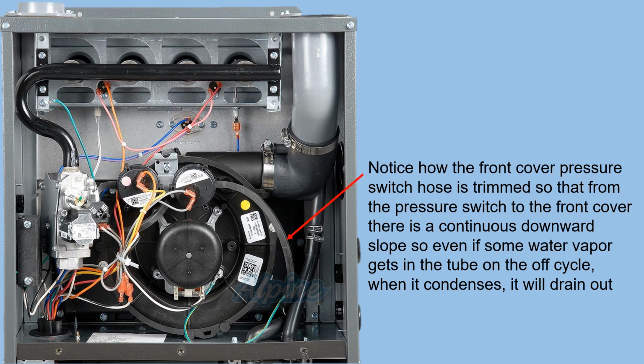Notice how the front cover pressure switch hose is trimmed so that from the pressure switch to the front cover there is a continuous downward slope. So even if some water vapor gets in the tube on the off cycle, when it condenses, it will drain out. And that's why also on the hose on your ignition pressure switch on the left, you don't want that sag like that, because when the furnace cycles off and there's water vapor moving around, it can move into that hose, condense, and it's going to drain, and it's going to run down into the trap that you've formed in that hose, and then your pressure switch isn't going to operate.